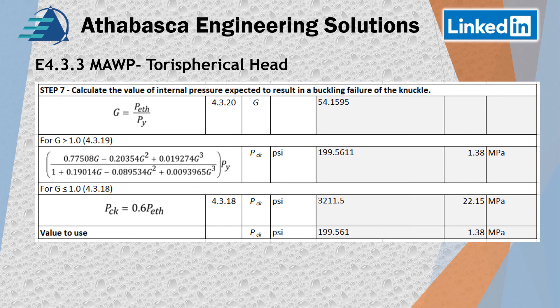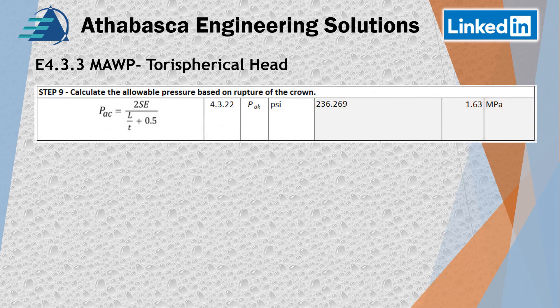Continuing for the next steps, we calculate the allowable pressure based on buckling failure of the knuckle, putting in the correction factor for safety allowance and reducing it down to 133 PSI — which matches closely to the example. In step nine we calculate the allowable pressure based on rupture of the crown. This is only available in Division 2, and we find it's quite a bit higher, which is what we would expect. So our vulnerability is at the knuckle.